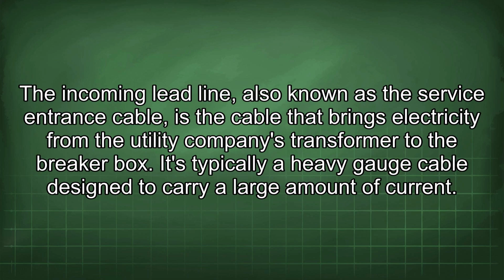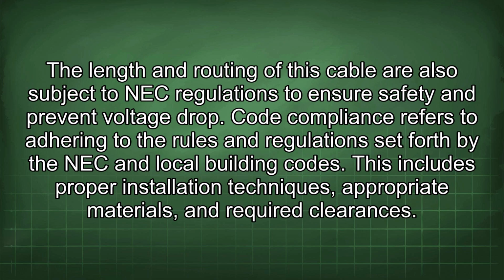The incoming lead line, also known as the service entrance cable, is the cable that brings electricity from the utility company's transformer to the breaker box. It's typically a heavy gauge cable designed to carry a large amount of current. The length and routing of this cable are also subject to NEC regulations to ensure safety and prevent voltage drop.